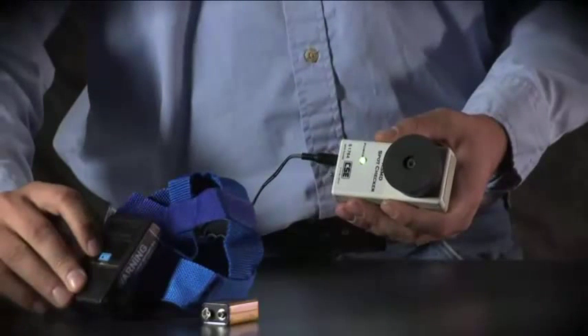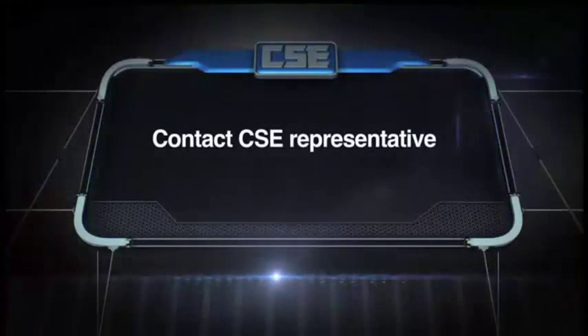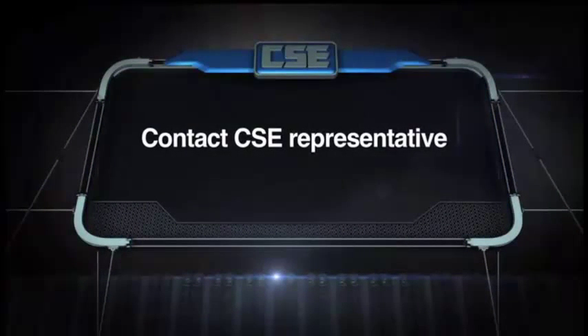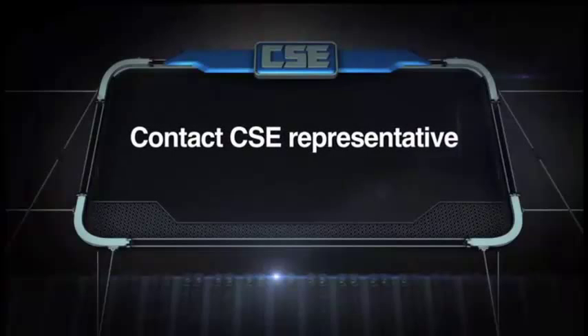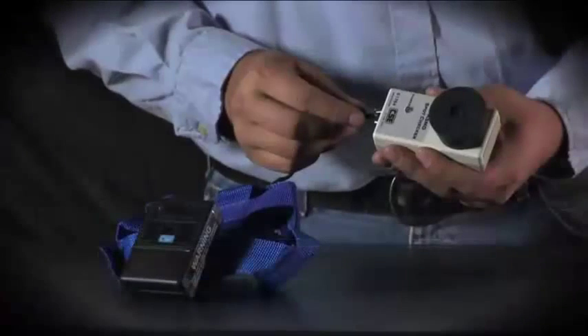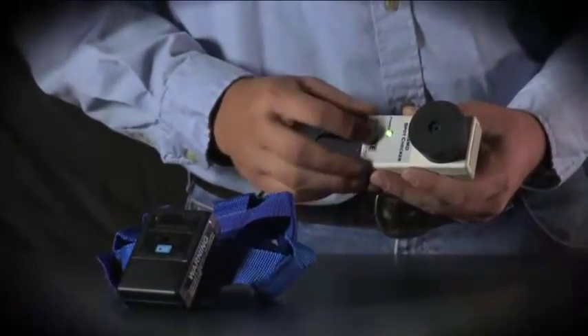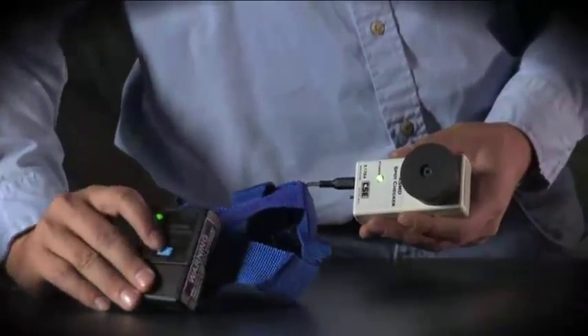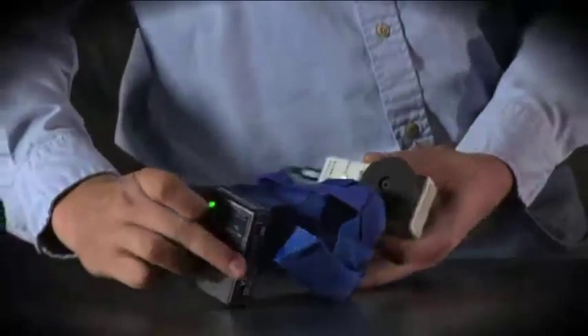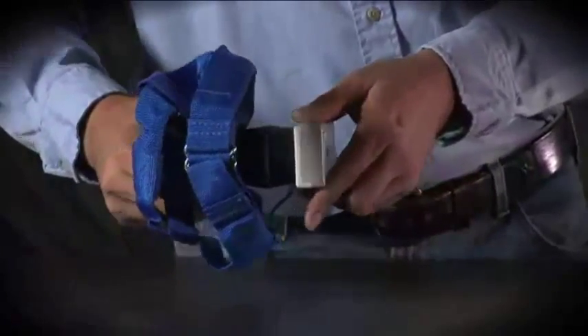The green power light will glow, and the spot checker will emit a high-pitched tone. If the power light does not glow, check the connections. If the spot checker still does not respond, don't use it. Contact your CSE representative and ask for repairs or a replacement. All set? Now, use the spot checker to test your ASMD's calibration. With the power switches of the ASMD and the spot checker on, join the two devices at their rubber cones, firmly enough to compress the foam layer of the ASMD cone. If the light on top of the ASMD glows red, it's calibrated and ready for use.